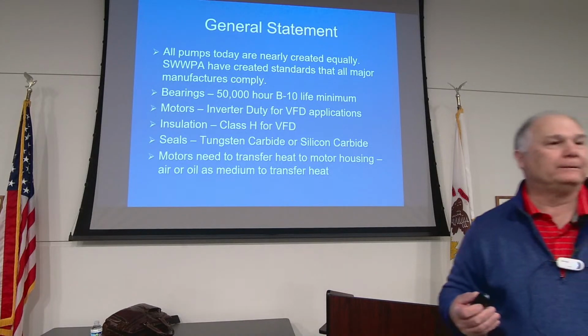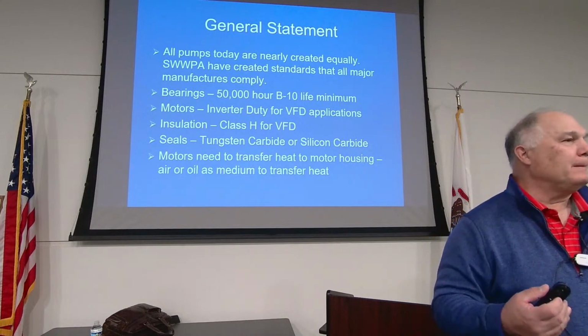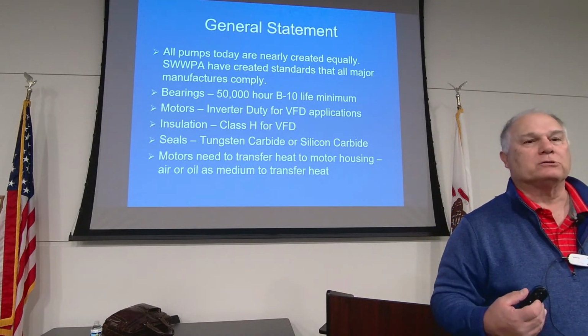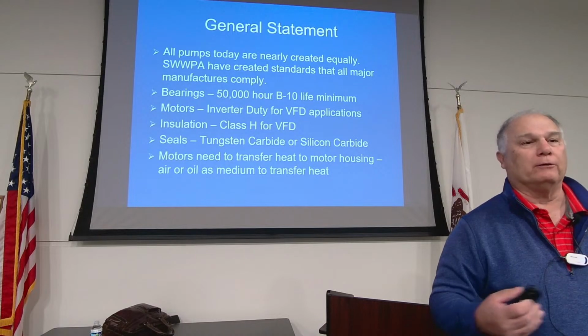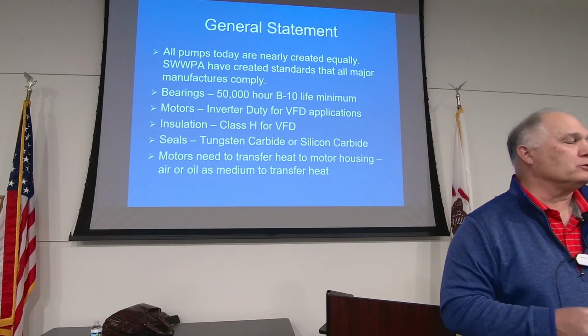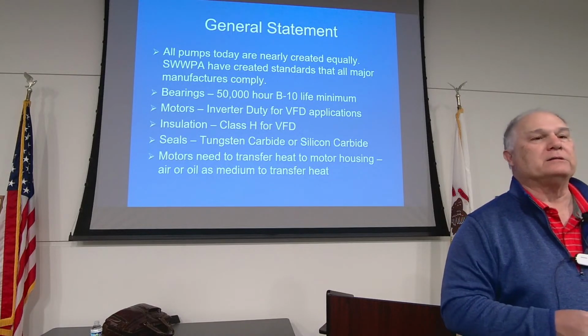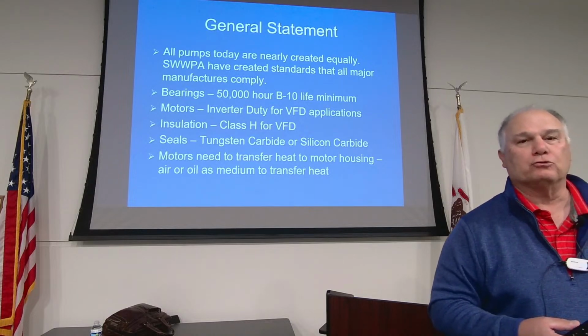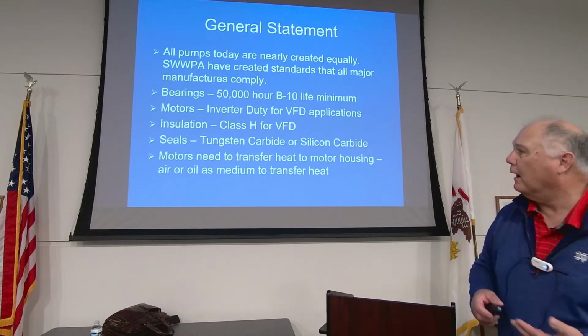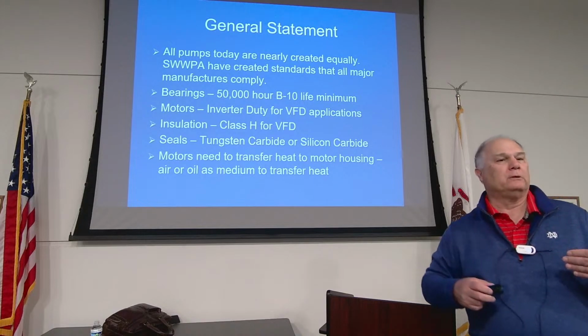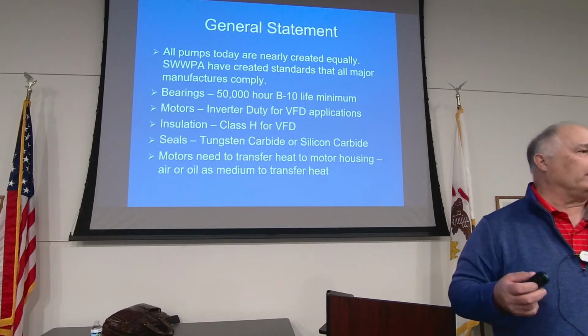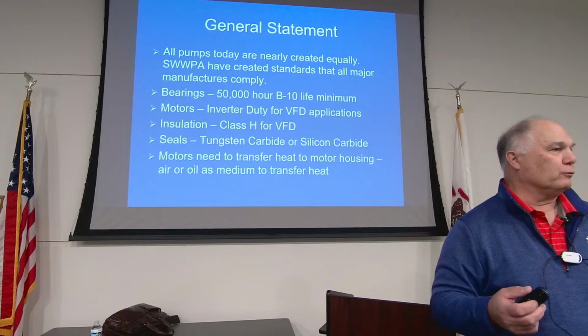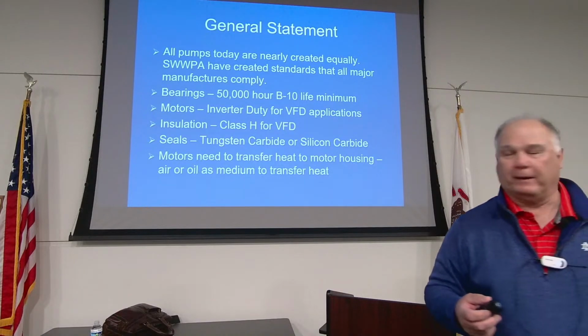Bearing life. In bearing life, the minimum would be 50,000 hours. Most manufacturers like Flygt, Sulzer, KSB have 100,000 hour bearing life usually in their pumps. Some of the smaller pumps don't, but they're not going to operate potentially 24/7 every day from that perspective.